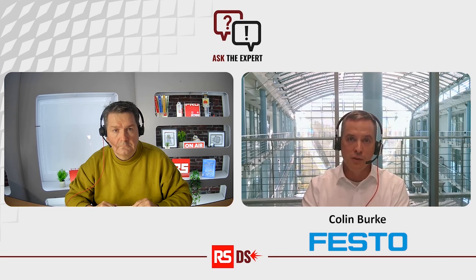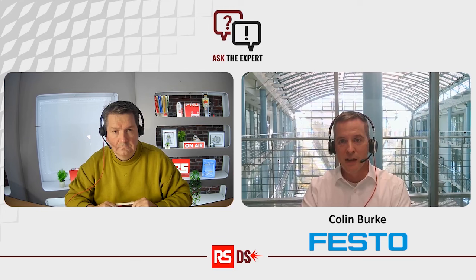And then moving on, we don't forget the programmer. Once you've got it all set up in Automation Suite, we appreciate that the customers don't really want to spend much time in Festo software. The whole machine will run on a Siemens or an Allen Bradley. So the Festo Automation Suite, once your configuration is done, with a couple of clicks, you go, please generate the function block and the description file for TIA, for example. And then you export that and you can import it into TIA, and then the programmer's back in his known environment. It pops up like a generic Siemens or a generic Allen Bradley or a generic Beckhoff, and you're away from the Festo software. You know it works, the initial commissioning is done, and they can do the cool stuff, making the total machine work. So that's huge time savings and ease of use for also programming guys.